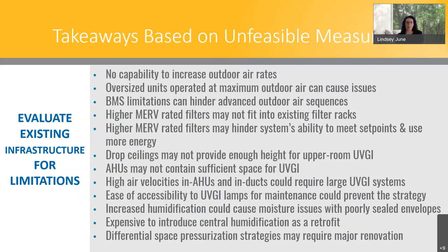And then major renovations may be needed to implement central humidification, such as new control and monitoring points for the BMS, a source of distilled or filtered water and electricity, and/or drip or drain pan retrofits. So spaces that have single zone equipment, such as schools with unit ventilators, may make it difficult to install a central humidification system since there is no central HVAC infrastructure already present. And then practical applications of differential pressurization may not exist due to HVAC zoning configuration, open space layout, and/or equipment limitations, such as exhaust fan capability or ductwork layout. So this also may require major renovation to implement and cause disruption to base building systems.